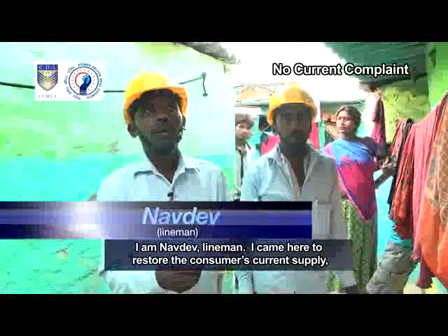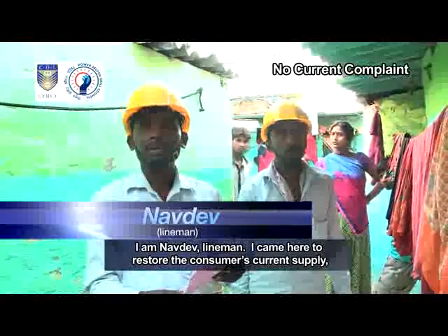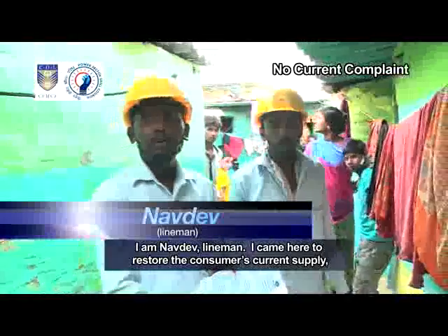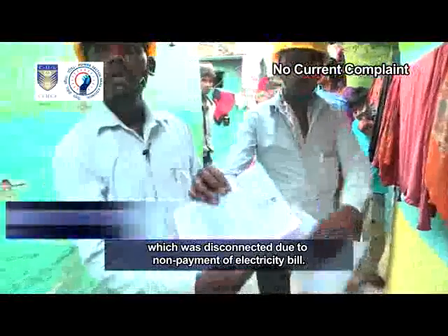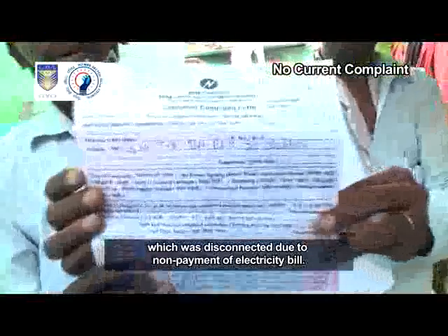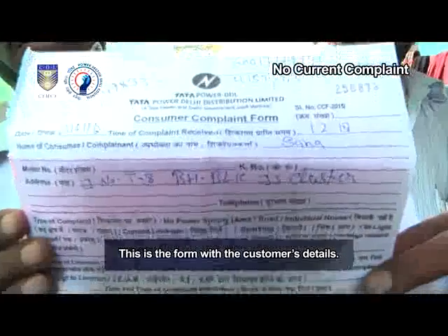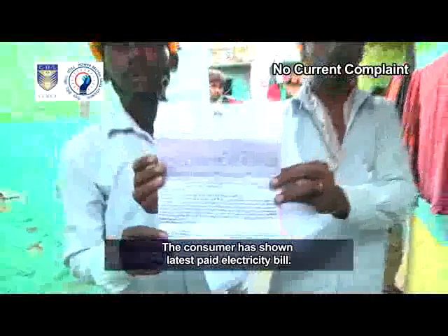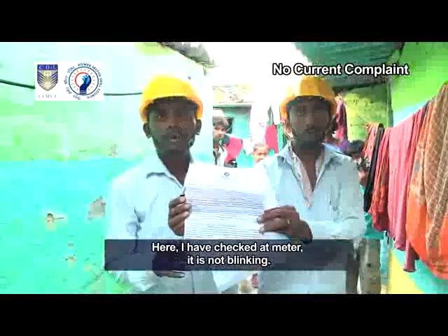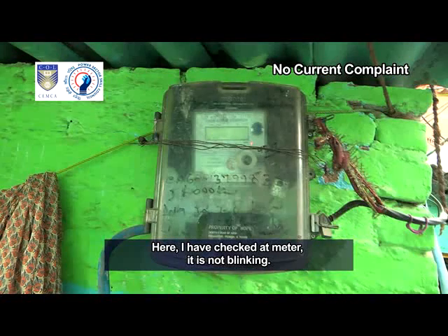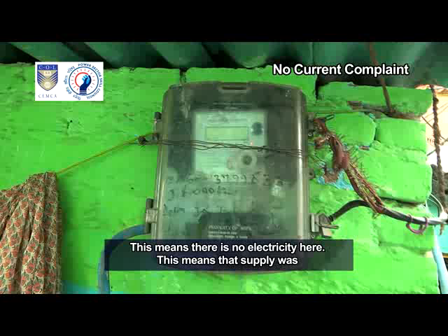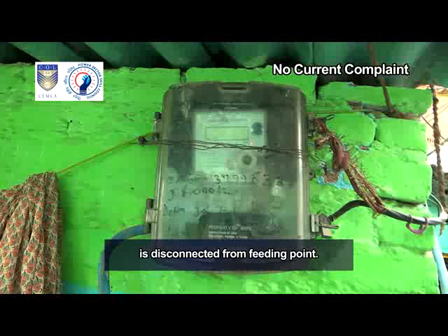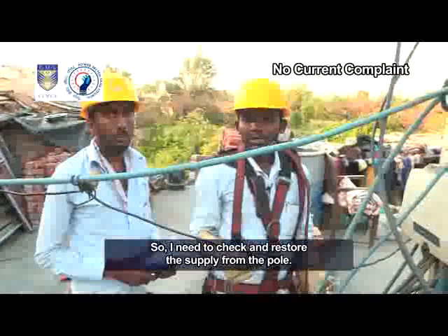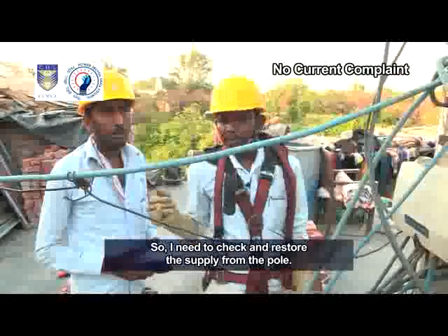I am Navdev, lineman. I came here to restore the consumer's current supply, which was disconnected due to non-payment of electricity bill. This is the form with the customer's details. The consumer has shown the latest paid electricity bill. Here, I have checked the meter. It is not blinking. This means there is no electricity here. This means that supply is disconnected from the feeding point. So, I need to check and restore the supply from the pole.